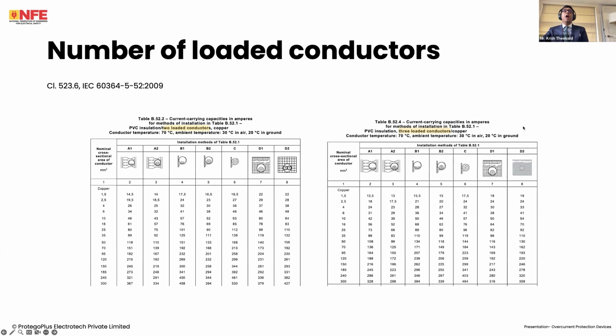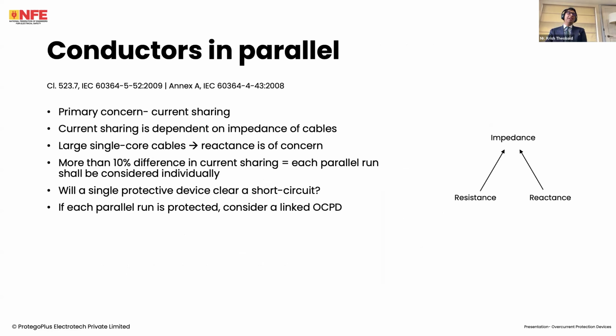Keep that in mind. Now, like I said, I'm not going to show you an example calculation because I keep showing it to you, but if there are any questions, you can ask later on. Now, some interesting considerations that we need to take into account. Conductors in parallel. Very often, for a smaller circuit, we can just run one line conductor, one neutral conductor, one PE conductor. However, on much larger sites, it may not be practical to do so for size and for maneuverability. When we do this, we may have two runs, so two line conductors, two neutral conductors, two PE conductors. This is most common in larger installations where you have, say, 630 mm² conductors per phase.